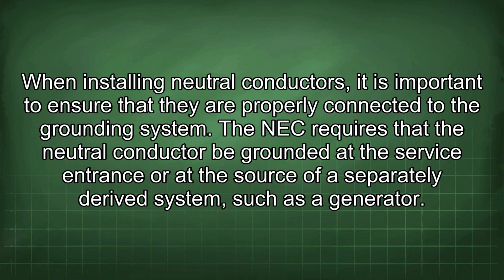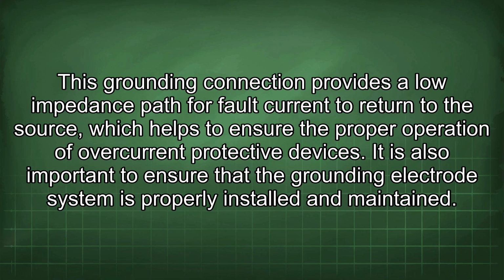The NEC requires that the neutral conductor be grounded at the service entrance or at the source of a separately derived system such as a generator. This grounding connection provides a low impedance path for fault current to return to the source, which helps to ensure the proper operation of overcurrent protective devices. It is also important to ensure that the grounding electrode system is properly installed and maintained.